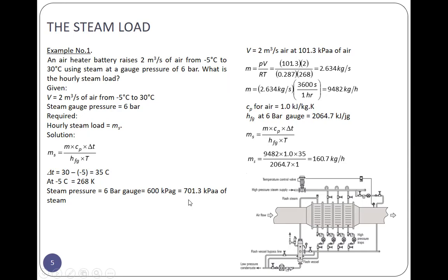So in your table, look for 701.3, that's the same. So M_s is equal to M times Cp times delta T over h_fg times t. So M_s is equal to 9482 times 1 times 35 over 2064.7 times 1 hour, which is equal to 160.7 kilogram per hour. This is the hourly steam load for 1 hour.